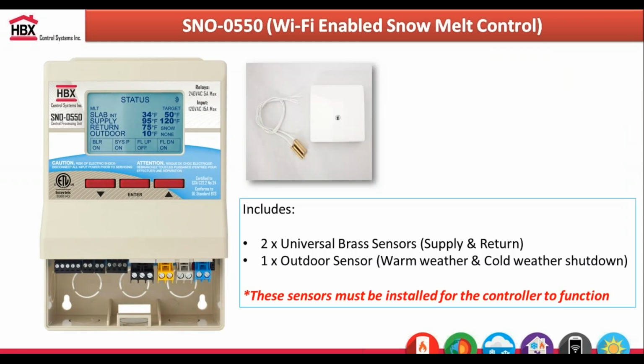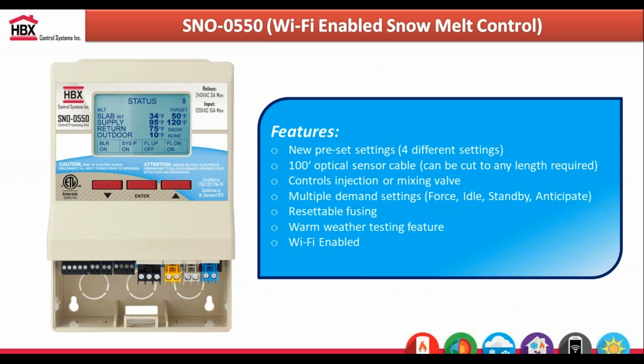With our controllers, we can give you all the sensors that are required for all our 550 controllers as well as our thermostats, so you don't need to buy any other accessories. We give you those sensors if you're going to use them for that controller or for another scenario. These sensors are just 10K ohm type 2 thermistors, for both the strap-on sensors as well as the outdoor sensor. In terms of the controller itself, again, we can control that injection pump for either valve or pump mixing.